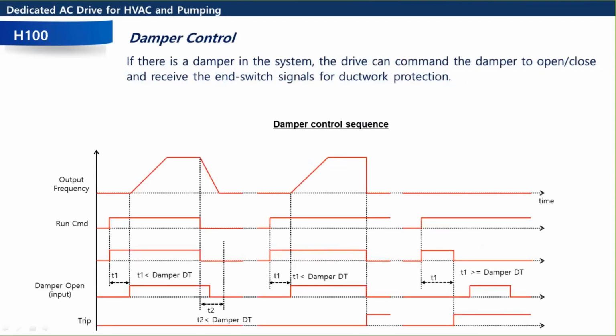Here's one of the HVAC functions here, which is a damper control. So if you think back to when we were talking about the relays, we have 5 relay outputs on the H100, and they're all rated at 5 amps. I believe they rated them at 5 amps, or put in the bigger relays, for stuff like this, where you can do damper control. A damper is just like a damper in a ventilation system that's opening and closing. So if there's a damper in the system, you can set up the drive to control the damper and also receive feedback via an end switch signal.